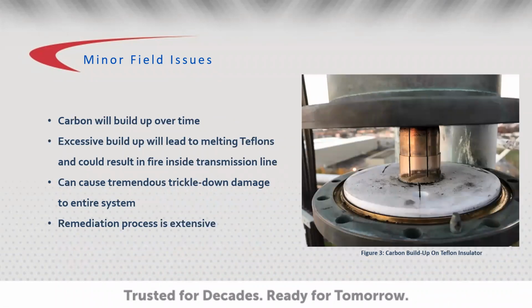In figure 3 here, we have a buildup of carbon material that can be seen on a Teflon insulator on a vertical section. So whatever happened, it was above it and fell down. This carbon material could have been the result of debris or dirt deposited in the system that was not cleaned prior to the powering of the system. Excessive buildup of the carbon material, if left untreated, can result in the melting of the Teflon insulator and potentially causing a fire inside the transmission line.